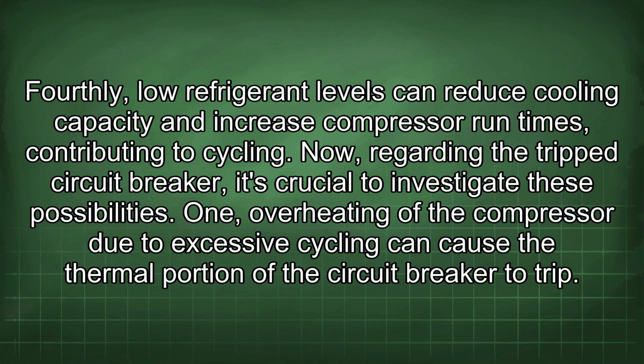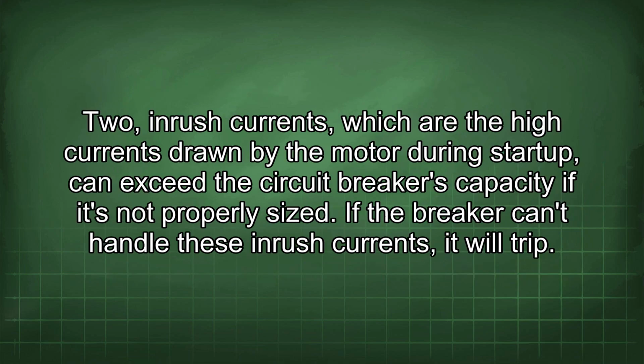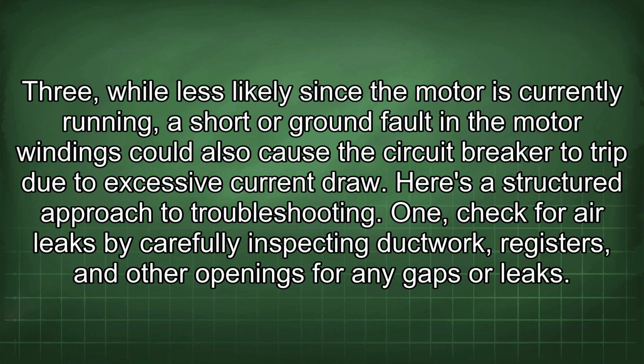1. Overheating of the compressor due to excessive cycling can cause the thermal portion of the circuit breaker to trip. 2. Inrush currents, which are the high currents drawn by the motor during startup, can exceed the circuit breaker's capacity if it's not properly sized. If the breaker can't handle these inrush currents, it will trip. 3. While less likely since the motor is currently running, a short or ground fault in the motor windings could also cause the circuit breaker to trip due to excessive current draw.